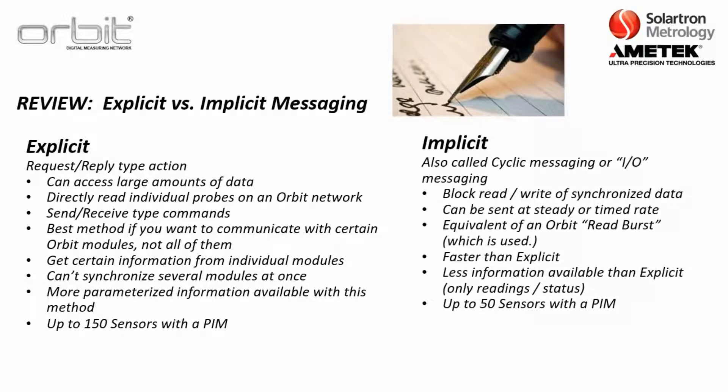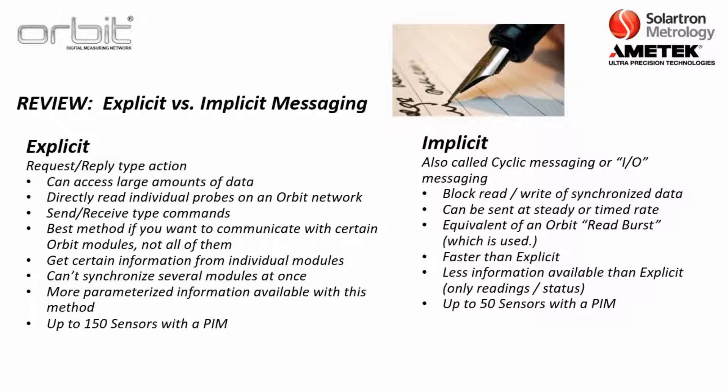Then there is implicit messaging, which is also called cyclic messaging or IO messaging. Now this is basically just a block read or write of synchronized data. It's basically equivalent to an Orbit read burst function and in fact that command is used inside the PIM to pull the data from the Orbit probes. So here you have synchronized readings being sent to the PLC. It is faster than explicit, but less information is available than explicit. So with the implicit mode you can do up to 50 sensors with the protocol interface module.